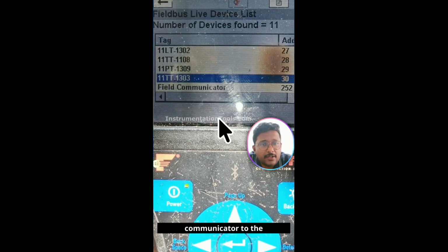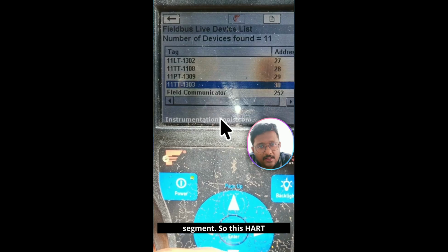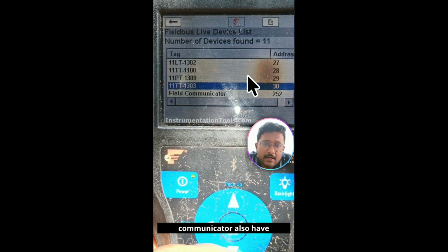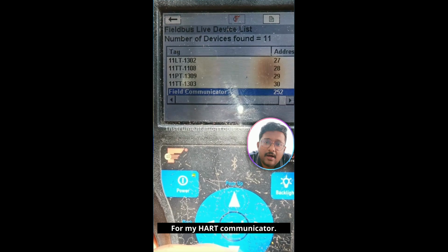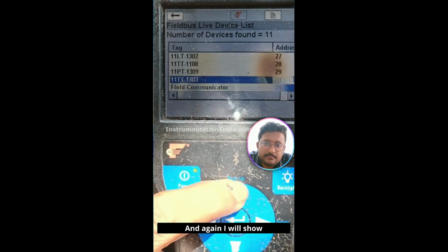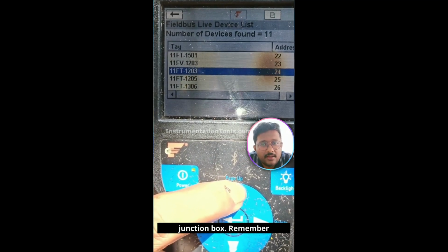So I connected my handheld communicator to the segment. This communicator also has a temporary node address. The Link Active Scheduler will assign a temporary node address or device address to a handheld communicator. In this case, 252 is a temporary address assigned by the Link Active Scheduler for my handheld communicator. And again, I will show you all my instruments connected in the junction box.